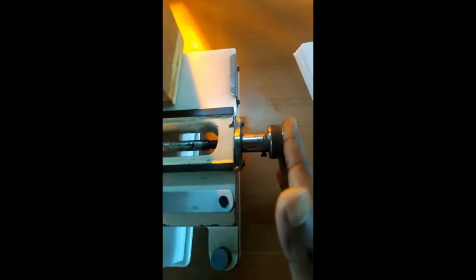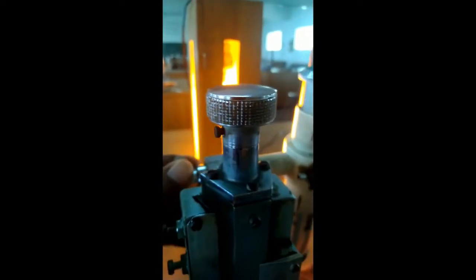Right? We can make this traveling microscope move horizontally as well as vertically. We do have 2 main screws and 2 tangential screws. This is the tangential screw for vertical movement, and this is the tangential screw for horizontal movement. And apart from that, the tilt of the eyepiece can be adjusted using this screw, and this is the focusing screw which adjusts the distance between the objective lens and eyepiece lens.